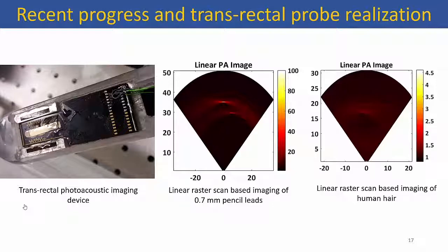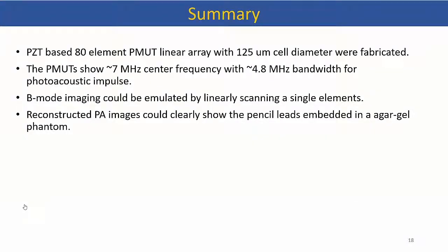With the linear scanning, we can already see it seems to be working — we can pick the image of a single hair and images from pencil leads. In conclusion, we fabricated PMUTs with around 125 micron cell diameter showing around 7 megahertz center frequency with 4.8 megahertz bandwidth. We used these for photoacoustic imaging by linear scanning and could detect pencil leads — the first step towards building photoacoustic imaging systems. Thank you. I thank NNFC staff at IISc Bangalore where I fabricated these PMUTs, my collaborators, and the funding agency.